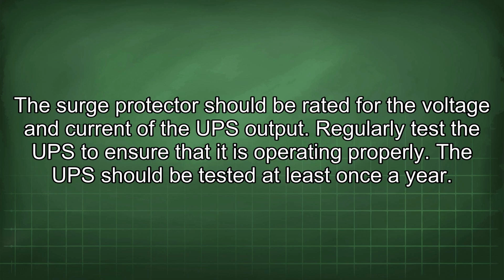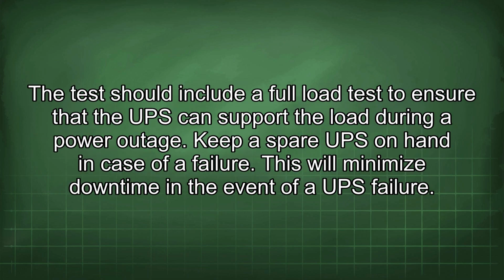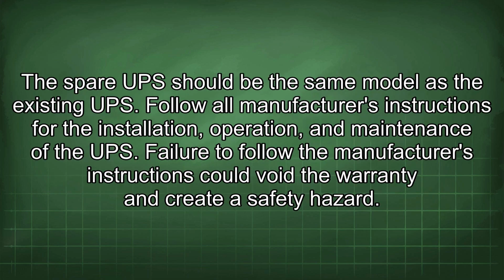Regularly test the UPS to ensure that it is operating properly. The UPS should be tested at least once a year. The test should include a full load test to ensure that the UPS can support the load during a power outage. Keep a spare UPS on hand in case of a failure. This will minimize downtime in the event of a UPS failure. The spare UPS should be the same model as the existing UPS. Follow all manufacturer's instructions for the installation, operation, and maintenance of the UPS. Failure to follow the manufacturer's instructions could void the warranty and create a safety hazard.